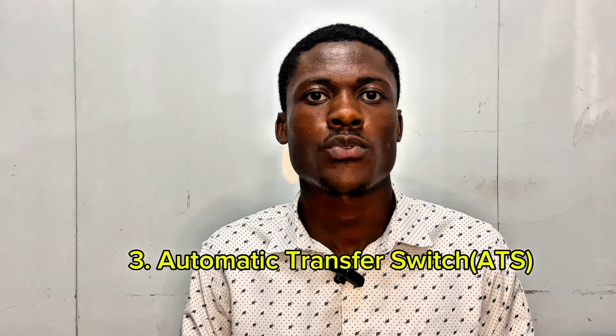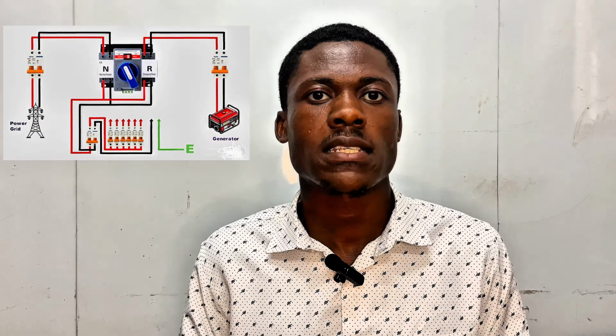That is the automatic transfer switch. Let's say we have two power systems, the power grid and the generator. We don't want these two power sources to be running at the same time. Hence, an ATS is needed. Whether it is a changeover or the automatic transfer switch, the circuit is going to change from one form of power to the other. Let's say you are using the power grid and there is a light off within that power grid system. The automatic transfer switch is going to automatically shut down the power grid and then turn to the generator or the solar. That's the ATS. With the manual changeover, you are actually going to switch from one power source to the other. That is that, guys. We have a lot of them, but I've actually given out three.